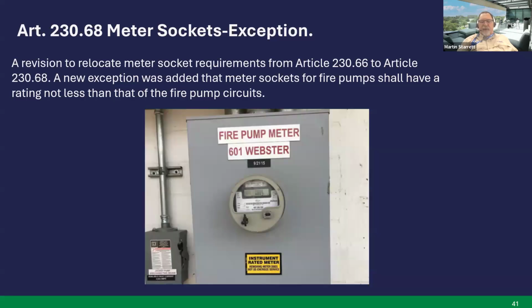Those of you that have installed fire pumps, usually the overcurrent protection devices can be rather large, especially if it's an instantaneous trip breaker. And if you're sizing your meter to the overcurrent device, then you would have a much higher, probably a CT meter or trans socket or something like that. This exception tells you that you only have to size the meters for the fire pump circuits. Now that's what the National Electrical Code says, but we, Austin Development Services, we enforce the National Electrical Code. Utility companies have their own set of criteria, and I can't respond to those.